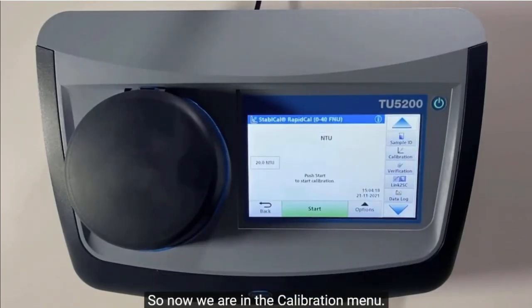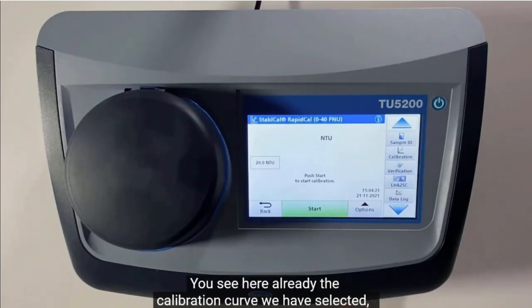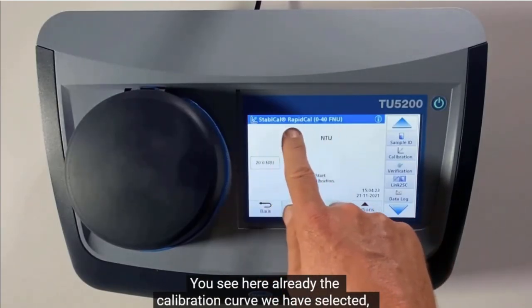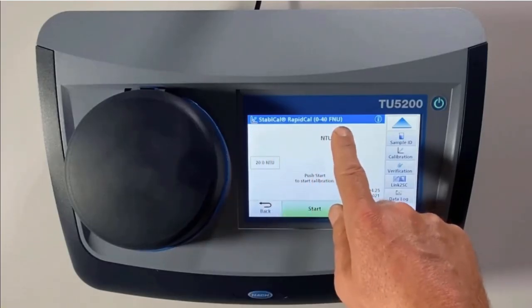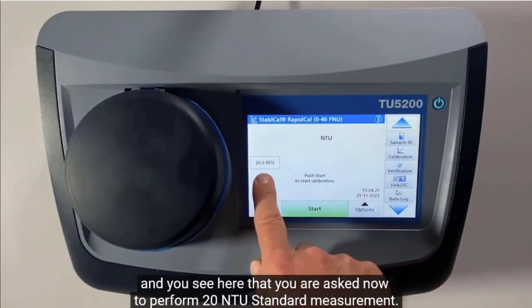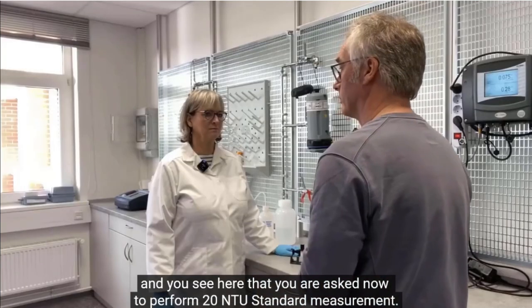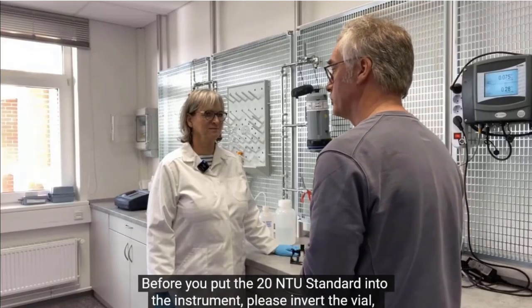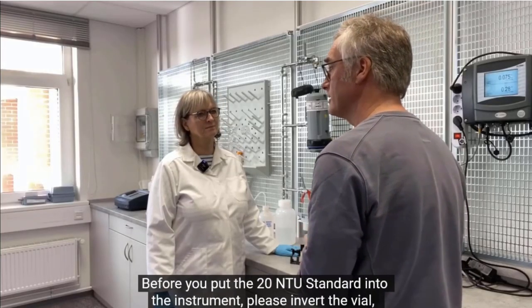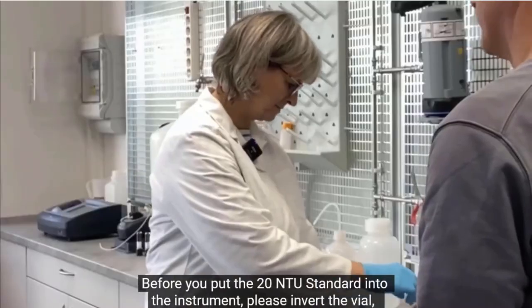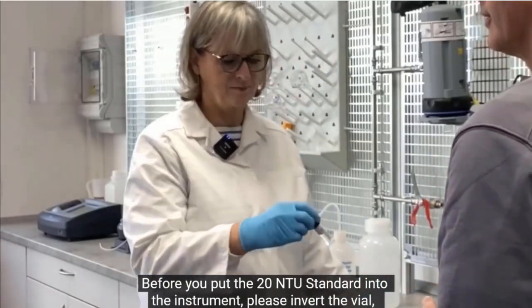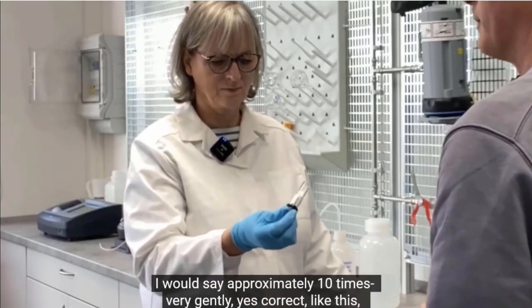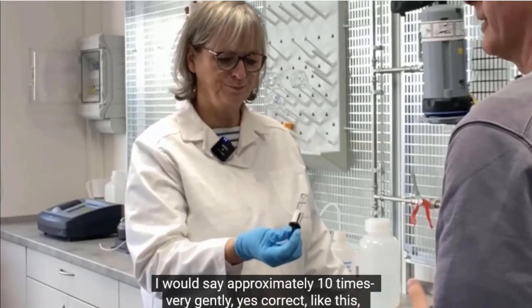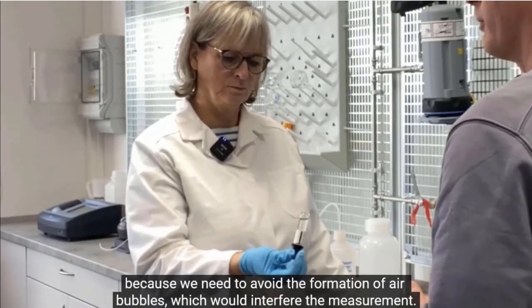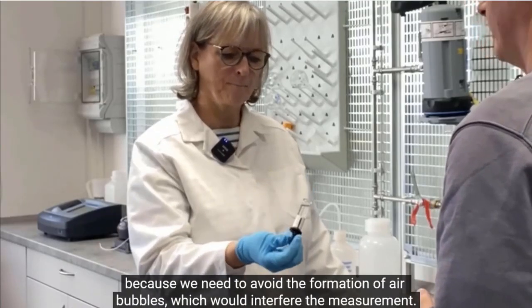Okay, so now we are in the calibration menu. You see here already the calibration curve we have selected. And you see here that you are asked now to perform the 20 NTU standard measurement. Before you put the 20 NTU standard into the instrument, please invert the vial, I would say approximately 10 times, very gently. Yeah, correct, like this. Because we need to avoid the formation of air bubbles which would interfere with the measurement.